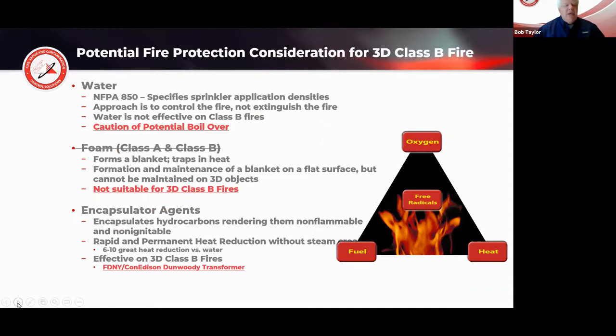So what do we know about 3-dimensional Class B fires? Well, we know that in NFPA 850, there are some specific sprinkler application densities suggested. We know that the approach really is to control the fire, not necessarily to truly extinguish the fire. We know that it's not necessarily effective on Class B fires, and there really is a potential, if it's dealing with oil tanks or even transformers, of a boil over condition that blows it all over the place and really makes things bad.